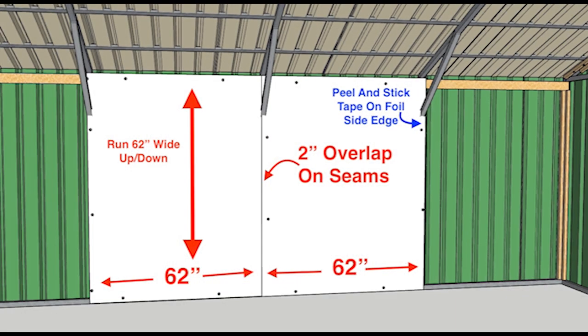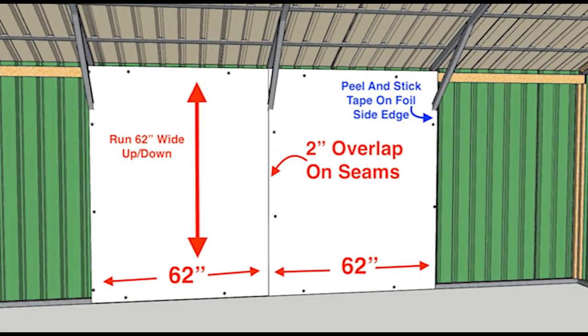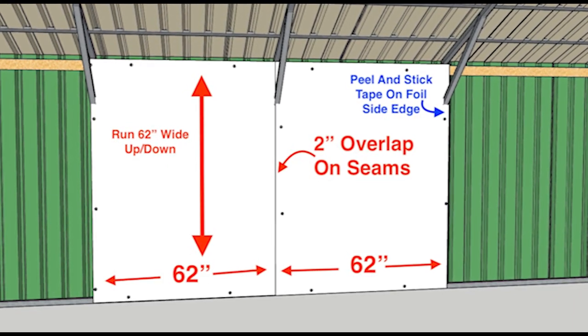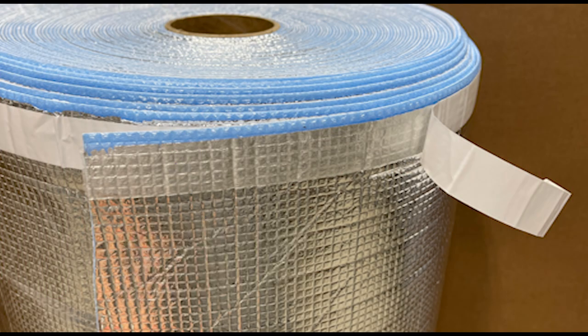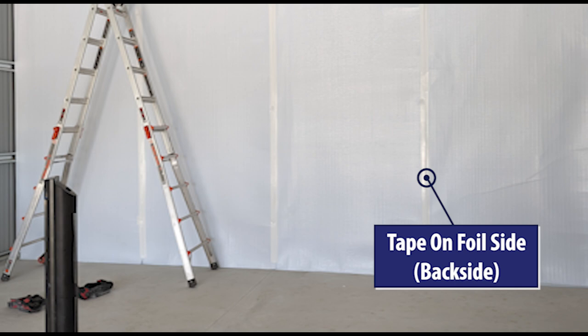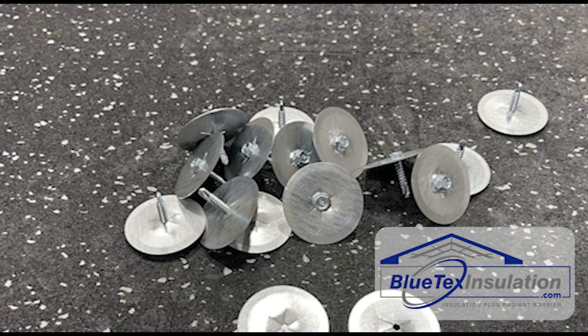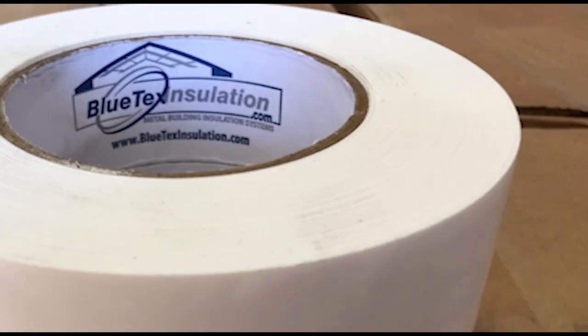As far as the install process, it's super easy with the 62-inch wide product. You're going to run it basically up and down on top of the framing. The BlueTex has a peel-and-stick tape on the foil backside, so you peel it and stick it to one side of the frame, then pull it over and attach it to the other side with screws and washers, which we can provide. Finally, you go back and tape the seams with a three-inch wide vapor barrier tape that we can also provide.